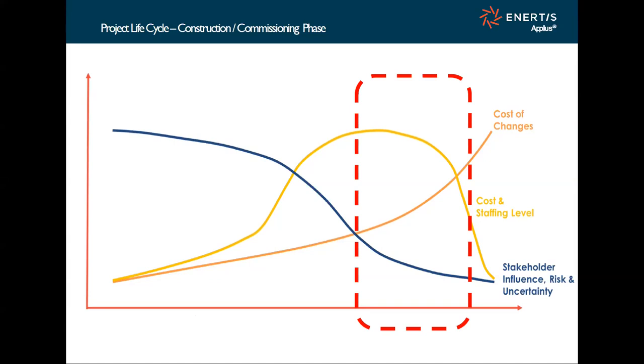Another piece, sometimes an afterthought, that I hope gets caught more during the design phase, is proper labeling of equipment—whether it's your battery containers numbered 1, 2, 3, 4, 5, or cables, conduits, and meters. Having equipment labeled as it arrives on site is really going to serve you well during troubleshooting and commissioning.